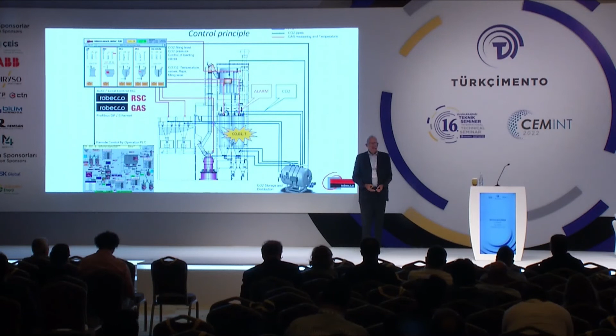There are two design methods, two tank methods available. First, on the left side, you see the CO2 low pressure system. It comprises a carbon dioxide tank and an ambient evaporizer in order to transfer the liquid CO2 into a gas phase before it is injected into the system. The operating pressure of this low pressure system is about 20 up to 23 bar. On the other side, you see this vertical tank—this is a high pressure system, with an operating pressure of about 50 up to 68-70 bar. The decision on what kind of system is used for different applications mainly depends on the ambient temperatures on site.